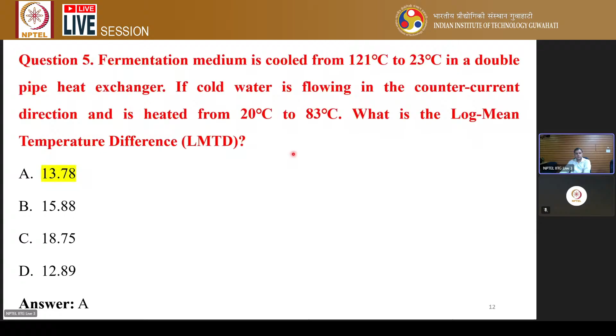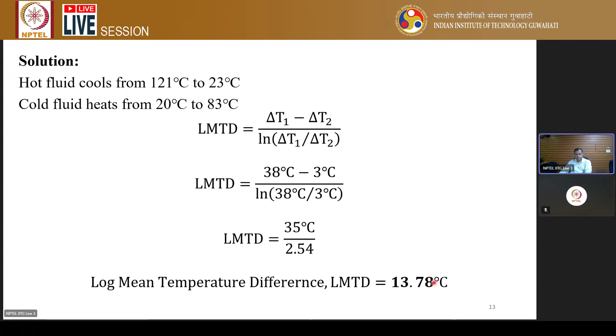So the hot fluid goes from 121 to 23, and cold fluid is heated from 20 to 83. For delta T1, consider this point: it will be 121 minus 83, which is 38 degrees centigrade. For delta T2, at the other side where it exits, it will be 23 minus 20, which is 3. In this way you calculate LMTD, and you get the log mean temperature difference as 13.78. This delta T will be used to calculate the rate of heat transfer.